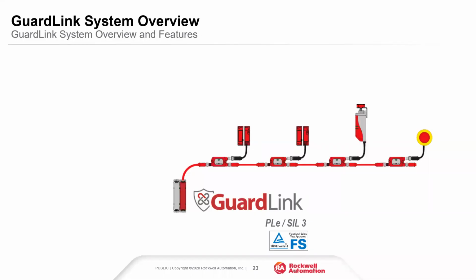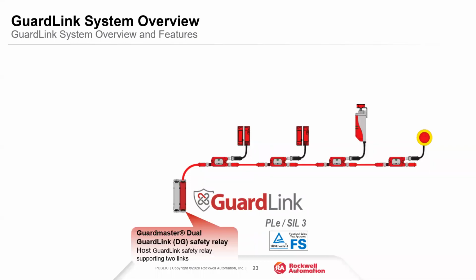So GuardLink, again, is what's used. It's a safety system, a safety network, that provides safety diagnostics. You can also do remote reset, lock and unlock commands over a standard cable. It's TUV certified. It's a trunk and drop topology, and it consists of a GuardMaster DG safety relay. That's a dual GuardLink safety relay, so you can actually put two GuardLink systems onto one safety relay. And each safety GuardLink system can handle up to 32 devices.